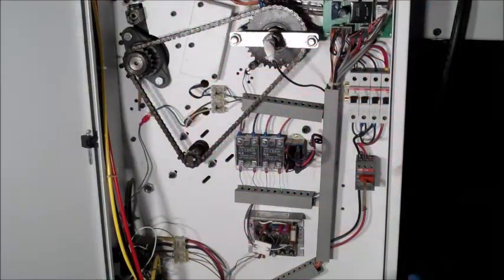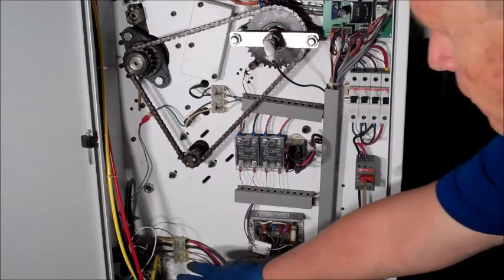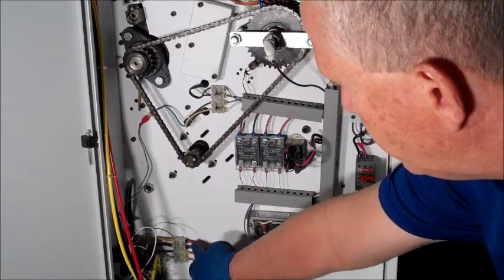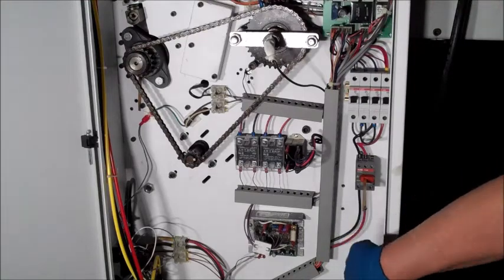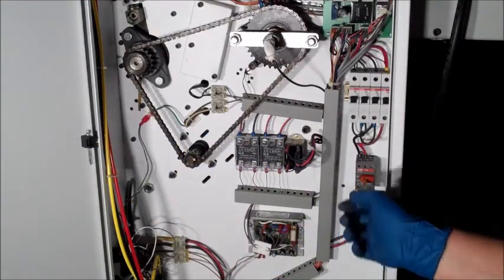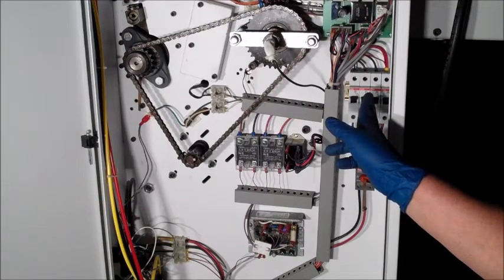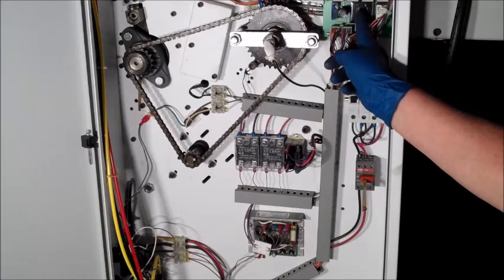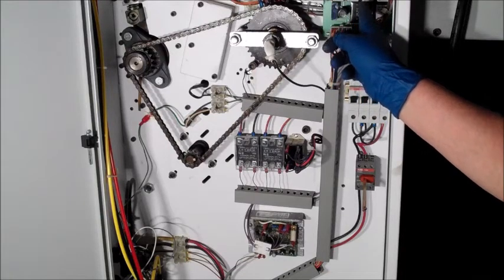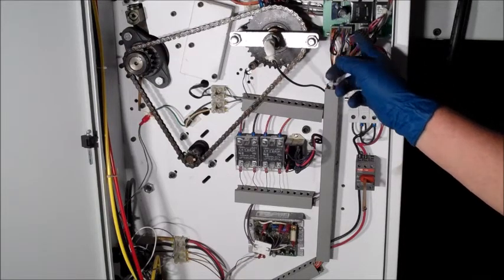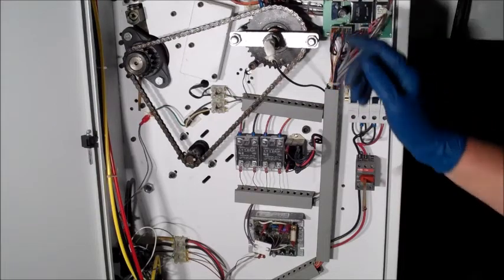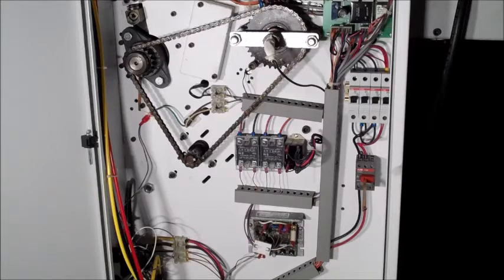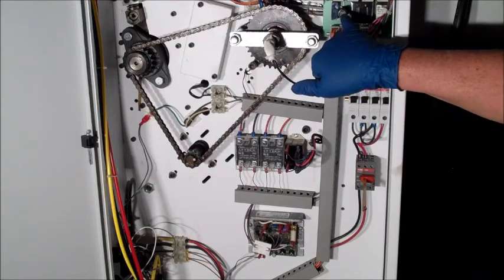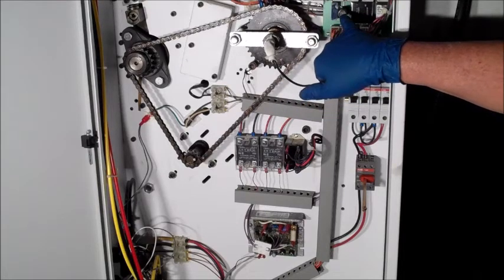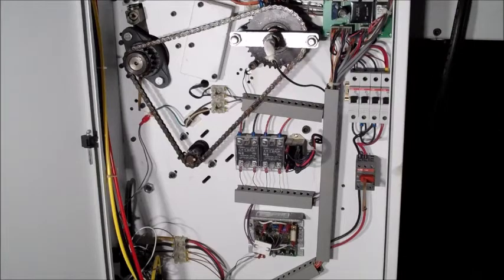On the Seal 600, you've got pretty much the same setup. You've got your service coming into this terminal block here, running through to the main power switch, which is in the door, and then circuit breakers for your 220. And then this board here is actually a combined integrated board between your safety circuits, and it is also your 24 volt power supply that operates some of the subsystems within the machine. On this particular unit, you do have one little fuse on that power supply board.